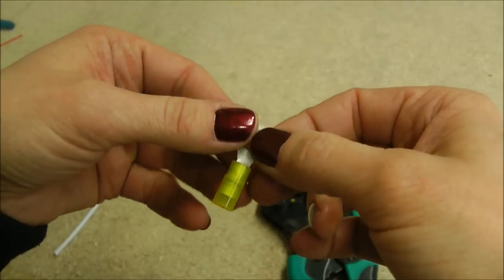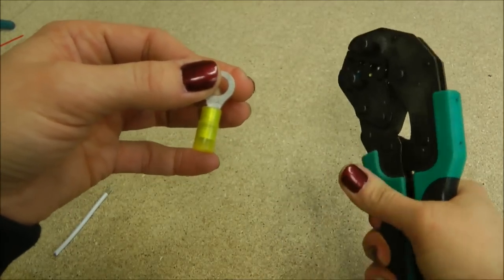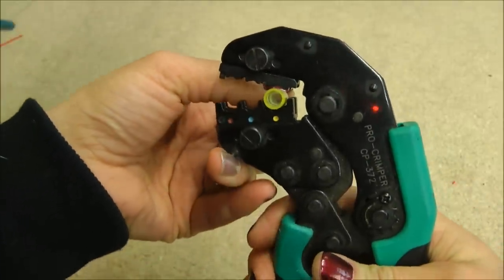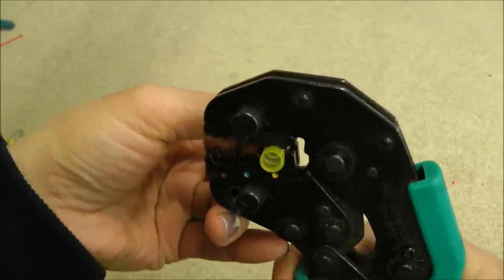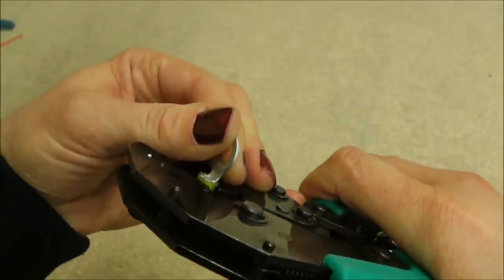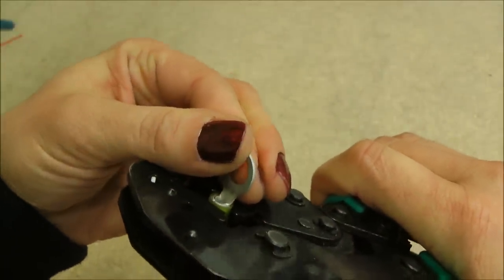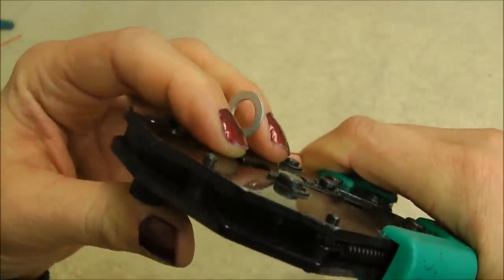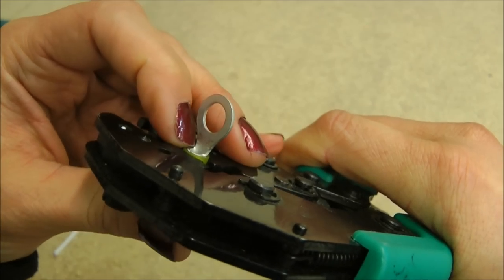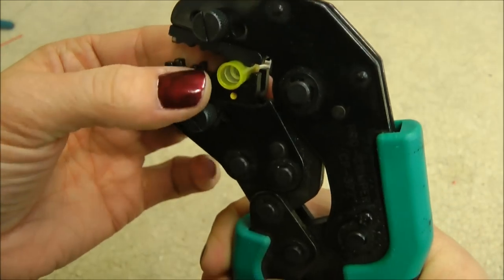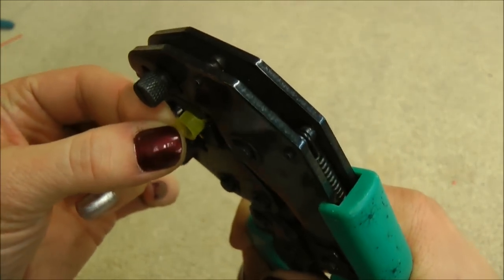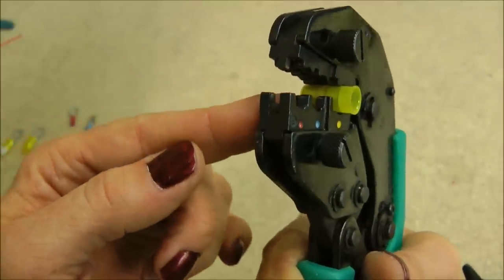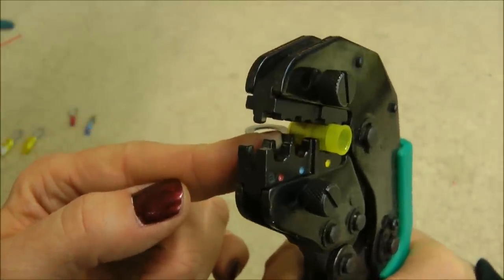I'll show you how to line up the terminal in the crimper and place it in the jaw that's appropriate for the size terminal that you have, this one being yellow, and put it in the yellow space. The back side here you want to make sure that it's lined up flush, that you just have a little bit of the barrel showing out the back side. Out the front you'll see just the plastic part of the barrel showing and that the whole metal barrel is completely inside the jaw and that's what you want.